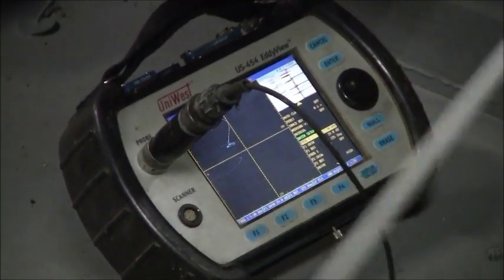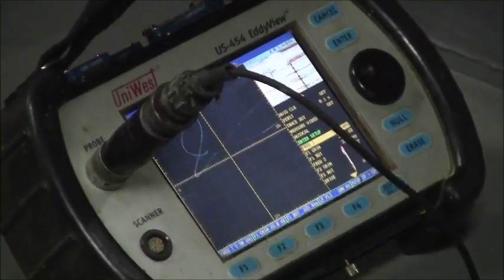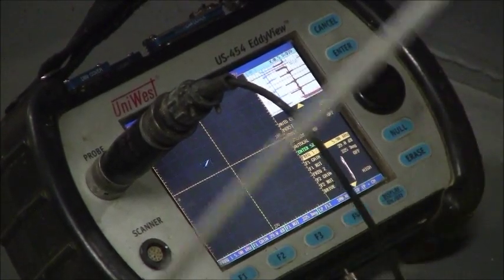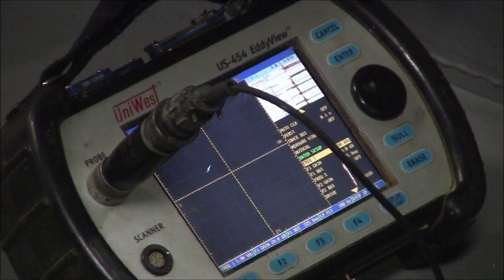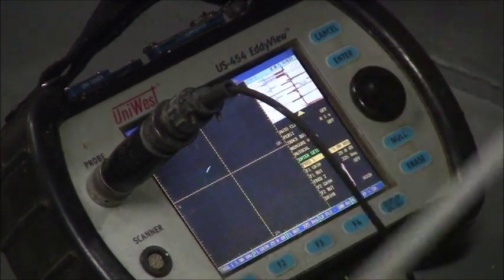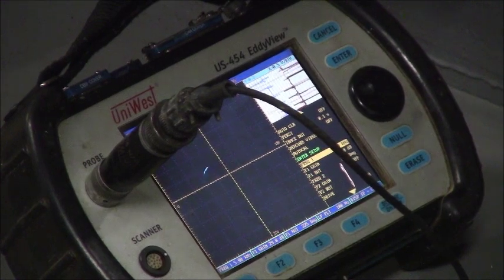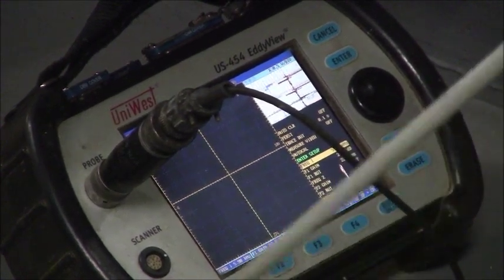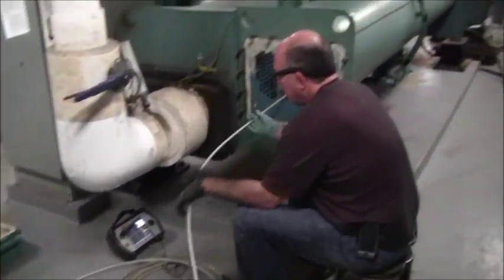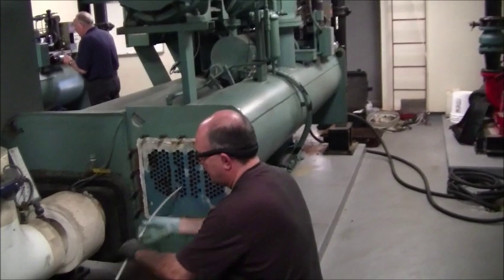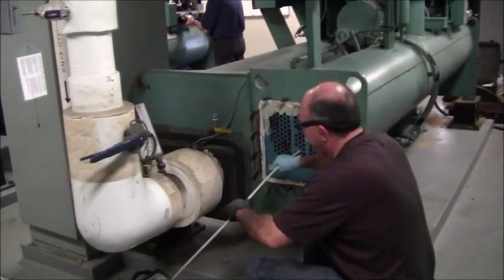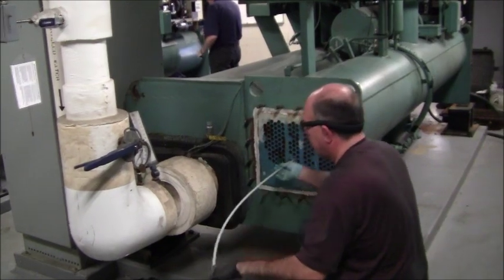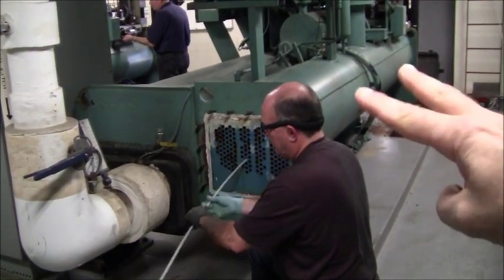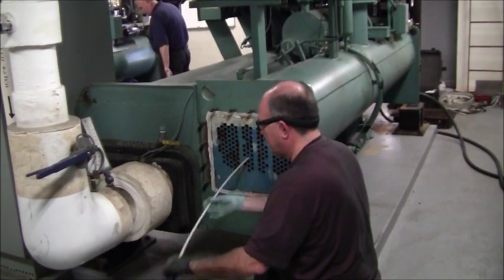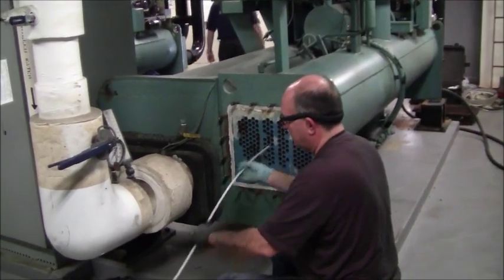Here is your machine. And it is recording, measuring the wall thickness and what's going on with the tube. So he can determine if there's a thinning situation going on, if there is some type of wear going on at the tube sheets. This particular condenser happens to have two supports in between. So it's got the tube sheets, one at this end of the shell, one at the other end of the shell, and then two support brackets that it has to go through in the chiller itself.